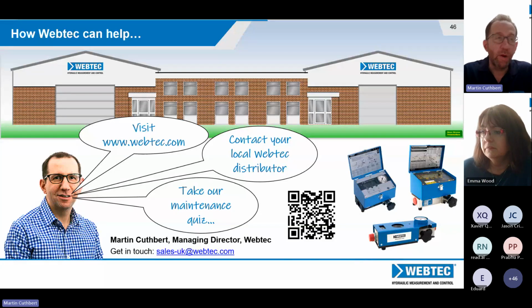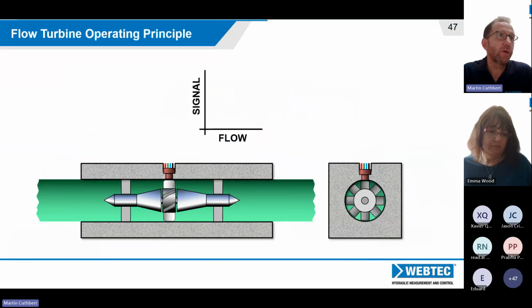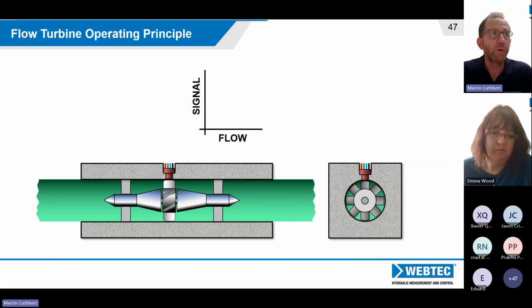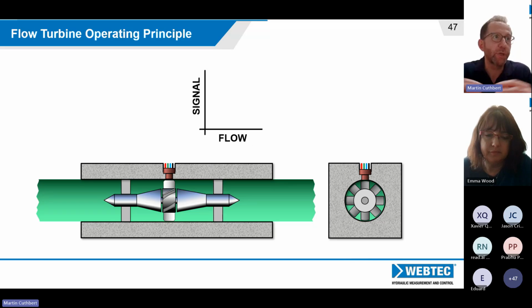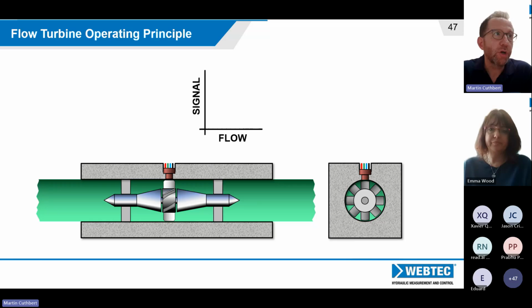Okay, let's start there then. I have a couple of slides in case something like that came up. I'm going to bring up a slide on turbine flow meters. Here's a section through a flow meter - if you imagine it lying in front of you, cut in half along its length, you'd see the turbine rotating on a shaft with a straightener on either side, and a pickup just above it with a signal coming out from that.